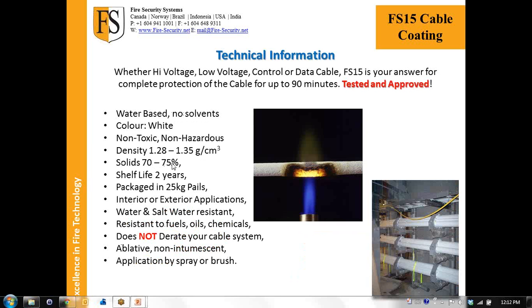So when we move along, the application of FS15 can be on high voltage, low voltage, control or data cable, any type of electrical cable, big or small, single or in tray, or simply bundled together with cable ties. It gets placed on the exterior surface of the cable bundle or the cable tray, similar to this trefoil application right here in the bottom corner. You'll see that the trefoils, which are 3 extremely high voltage cables, we just coat around the external surface of it. And we coat around the external surface because the flame spread is coming from another region.